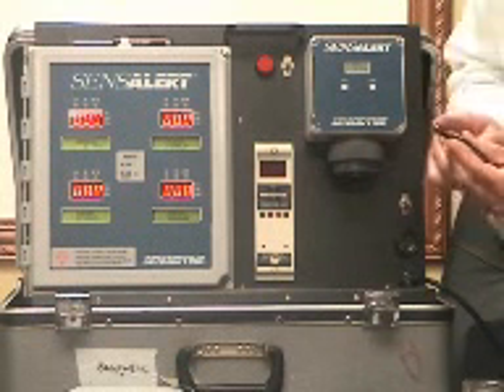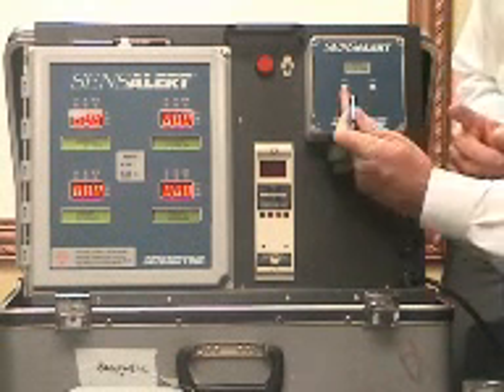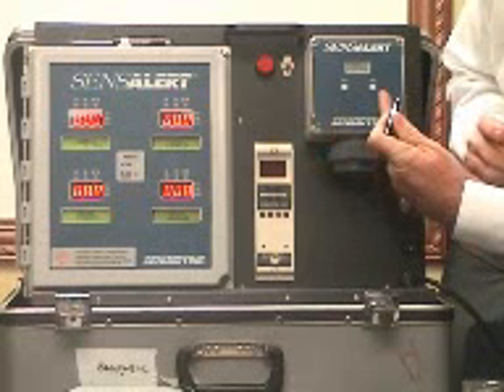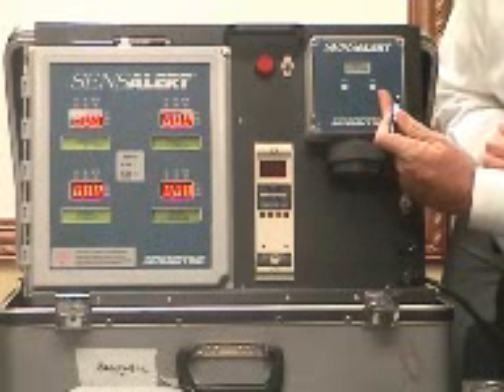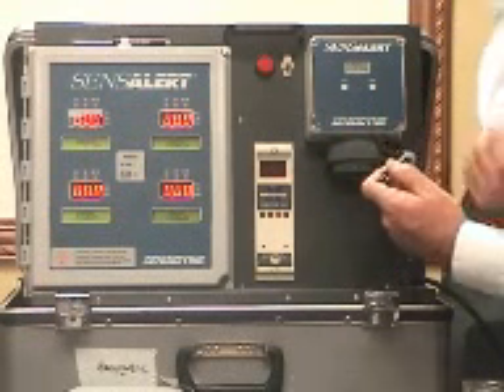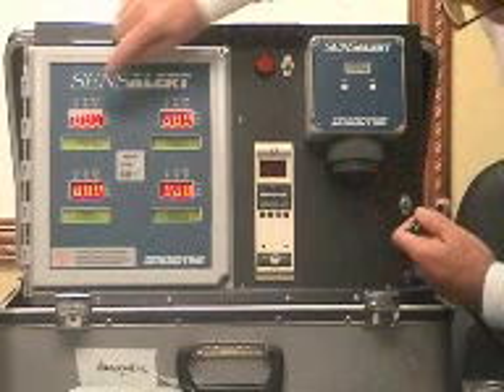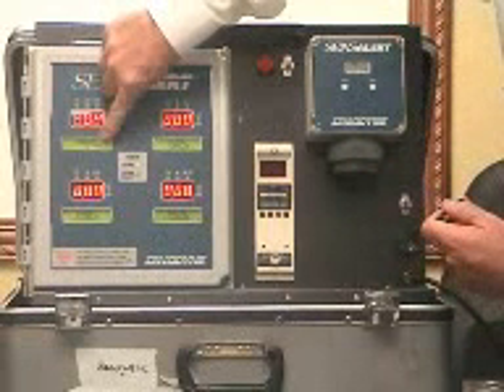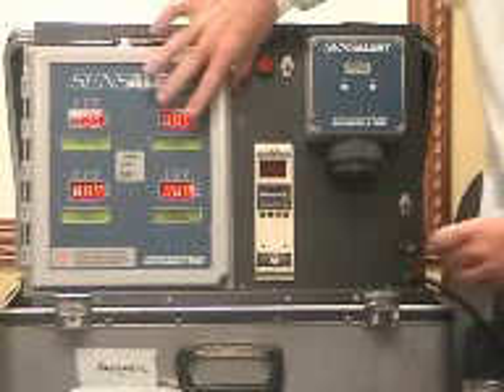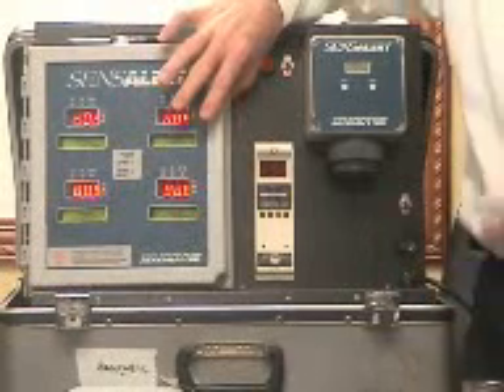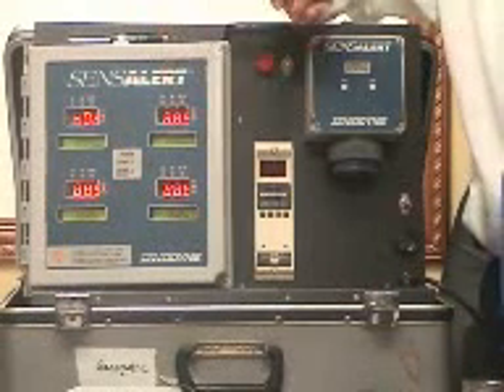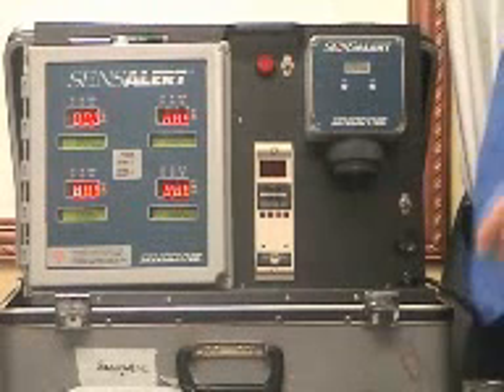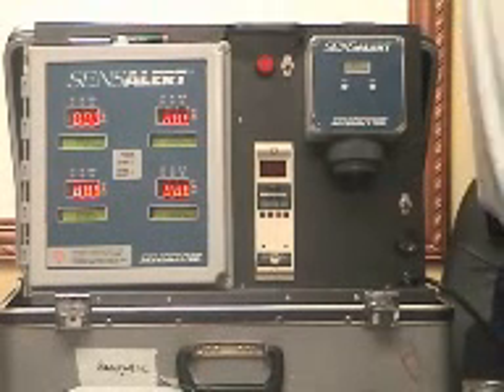Just the magnetic screwdriver. You touch the button here that says 0, or the button here that says span, to put it in cal mode. It says NH3 0, NH3 or ammonia 0, and all the sensors except the oxygen have only 2 alarms, low alarm and high alarm, deficiency and enrichment.